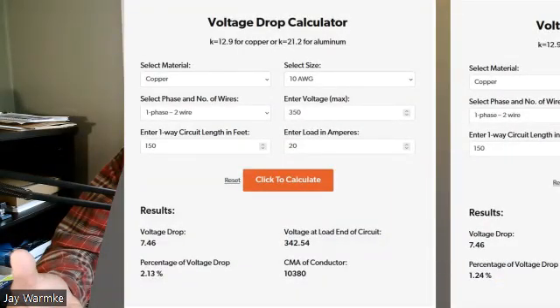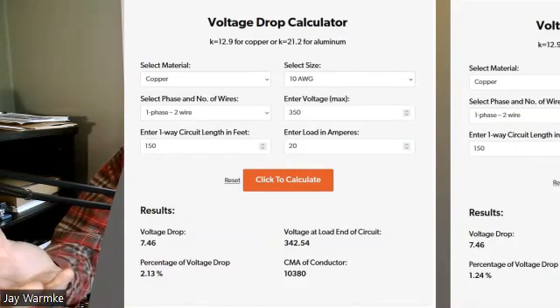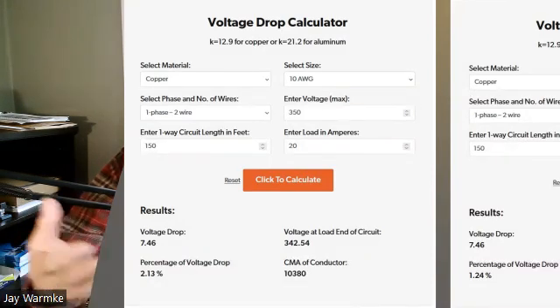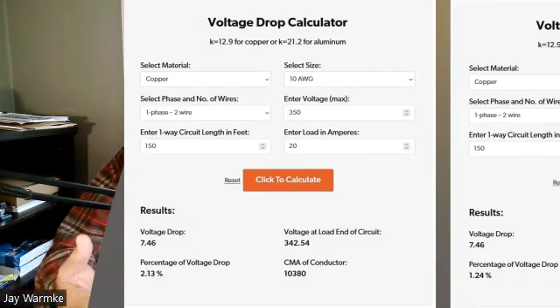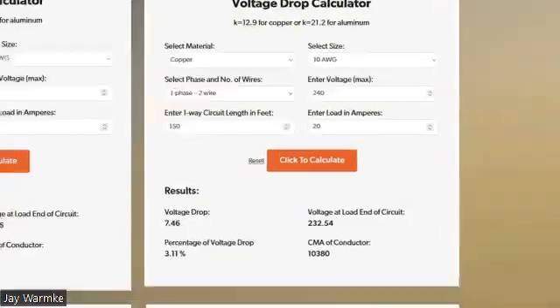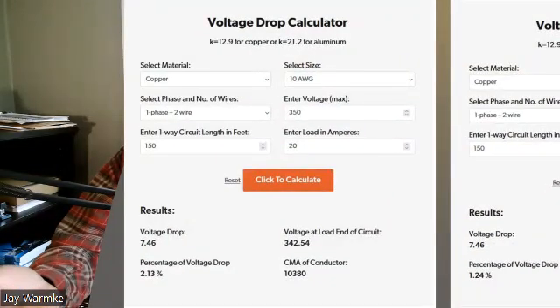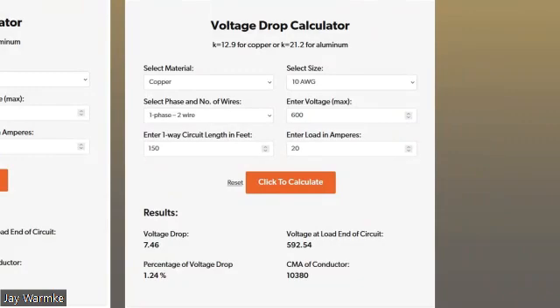Another thing we could do is say, all right, let's say that this is a SolarEdge system versus an Enphase. Well, the voltage that's gone up is 350. It's going to be operating at 350 volts, not at 240. Well, it doesn't change the voltage drop. Notice for 10 gauge cable, it's still 7.46, and up here it was 7.46 voltage drop, but it's a lower percentage of the amount of power that's being lost. And then if we go to 600 volts, like for a string inverter of some sort, well, it's still the 7.46 volts, but it's only 1.24 percent of the power loss from start to finish. So that's kind of where we are with voltage drop.